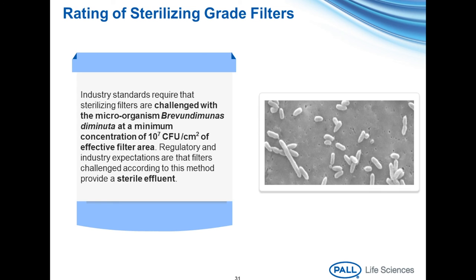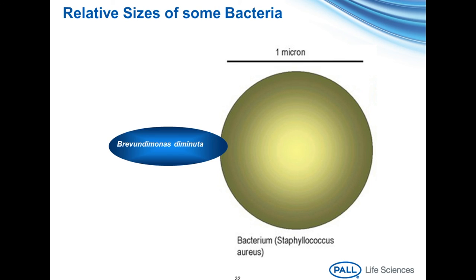Brevundimonas diminuta, often called B. dim, is a very small gram-negative rod bacteria. It was chosen as a reference test organism due to its ubiquity, its small size, and the ease of culture. It's important to use a test organism that is small, but also one that is easily cultured so you can be sure you can detect it if it does get through the filter. This slide also shows how it compares in size relative to some common pathogens.